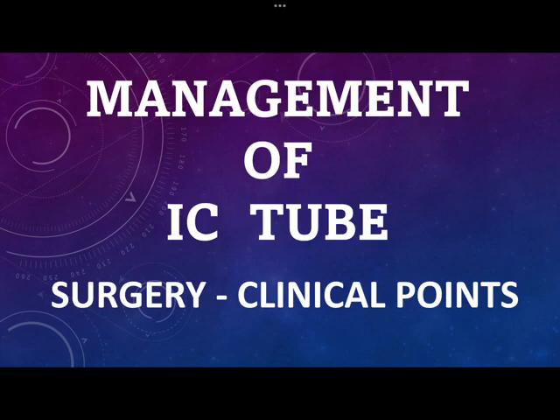Now the suction apparatus makes the suction very high. So you don't want that to happen. That is why this apparatus is there, right? So what this does is, what they say is to have minus 20 cm H2O of suction pressure, minus 20 cm H2O of suction pressure for the lung to get properly expanded.